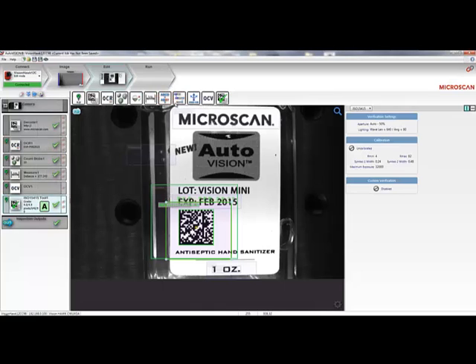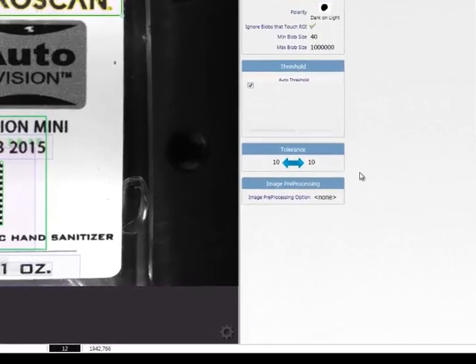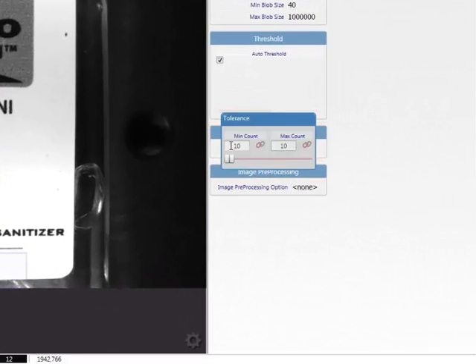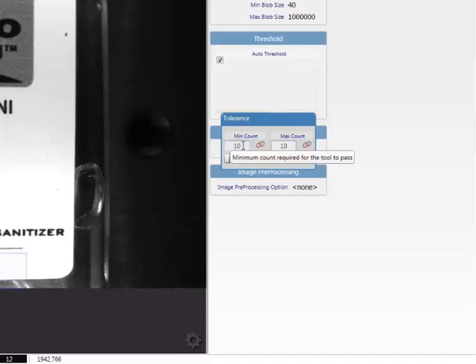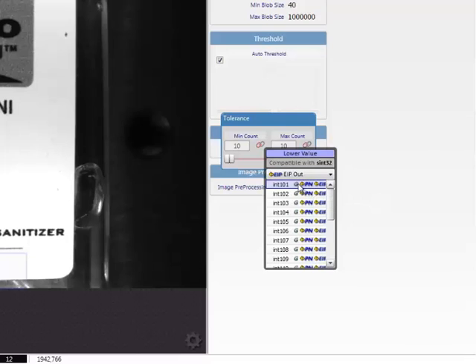The next step is to make the data from my machine vision job available to the outside world. For example, I can communicate my inspection results to a TCP IP interface, or a PLC system, or to AutoVision's CloudLink HMI interface. In order to do this, I will use AutoVision's connectivity feature called MicroscanLink. First, I'll link the tolerances of my Count tool by taking the parameter and clicking on the MicroscanLink icon here. This allows me to link the parameter to a PLC system over protocols such as Ethernet IP or Profinet IO. MicroscanLink also makes outputs from this tool available for general use on the Serial or TCP IP interface.